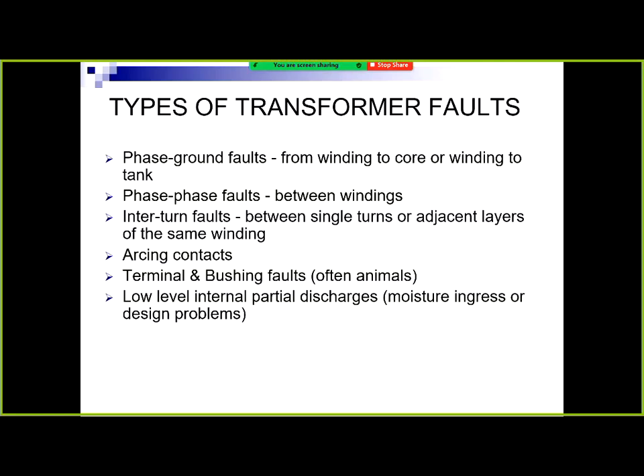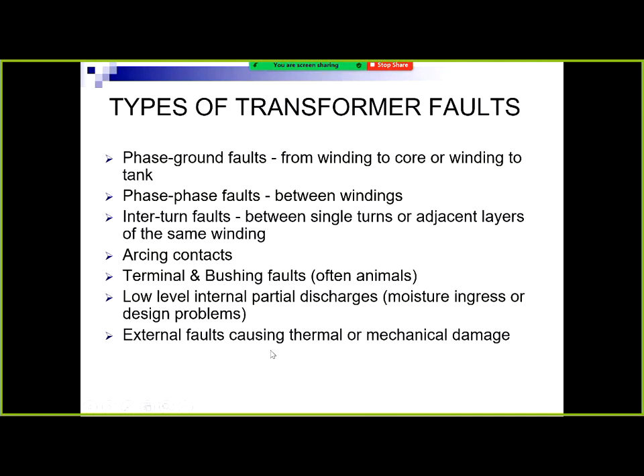happen very much in Powerlink. We've got a couple of smart engineers who've been there for decades. We specify our transformers, go to the factory and see each one made, witness all the tests, so they're very rigorous. They're rigorous to the point that we buy a certain manufacturer's transformer from a certain factory. We won't buy that same manufacturer from a different factory. So they may have 5 factories around the world and we'll only buy from 2 of them. So we tell them we don't want that. We're not going to buy yours from those factories, they're excluded. So we go to that level, so that sort of issue is not so much a Powerlink problem, but can be a problem for transformers in general, as a generalised comment.